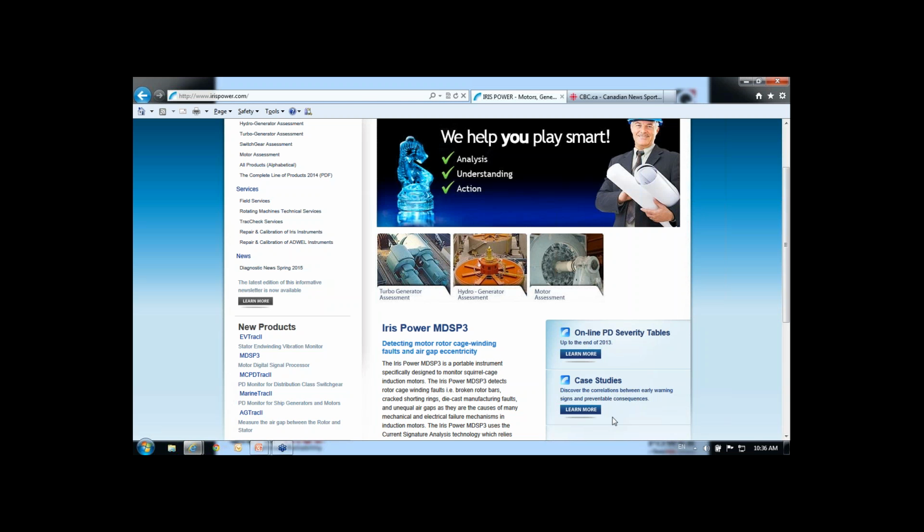Okay. Do you recommend some limit of QM measurement on offline tests for new windings or individual coils? We wrote a couple of papers on this subject, and there are some guidelines, and even the IEEE 1434 guide will say something, but not in QM; it will say it in milliamps, as a corona probe sensor approach. But it is difficult to recommend anything. Some OEMs, some manufacturers, will have their own in-house standards, but they might not be expressed, measurable or repeatable. So the answer is, in short, no.